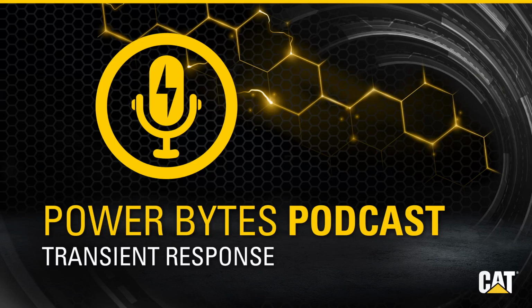Some customers may only have 500 kW of load, but because of the transient response they need, the system may recommend a 750 kW generator set. SpecSizer is very helpful in making sure that you get the product that you need to support your application rather than getting a product to the site and finding out you have an issue.